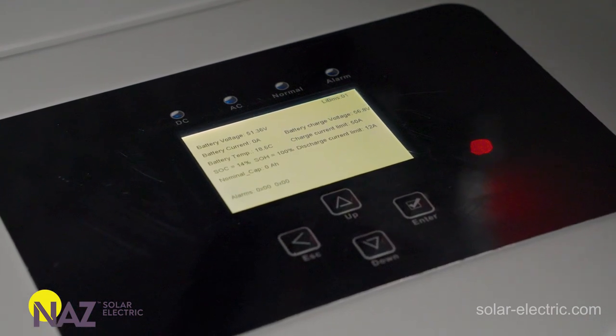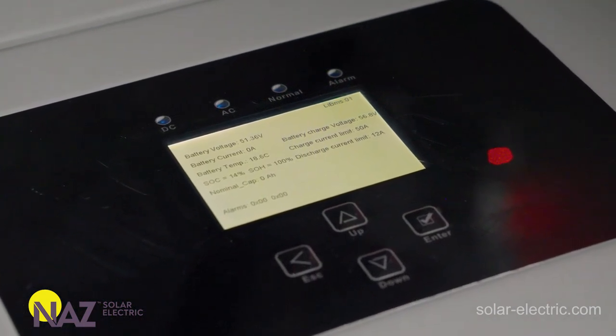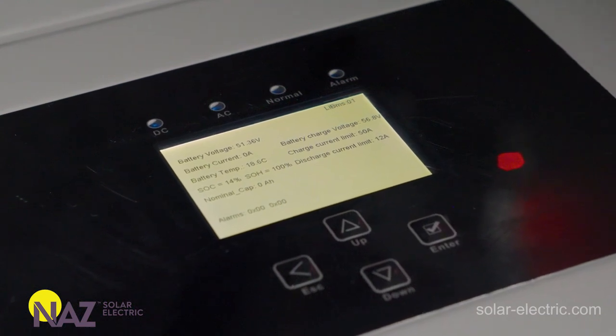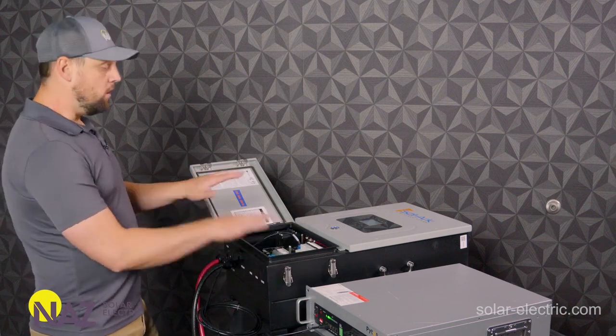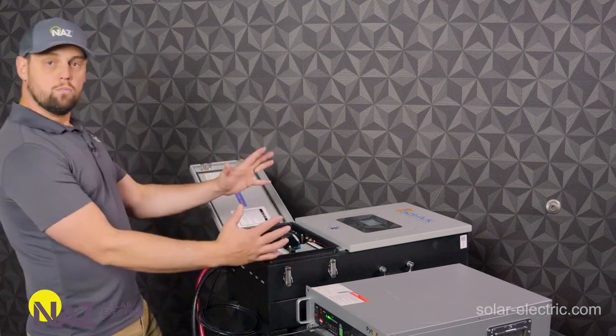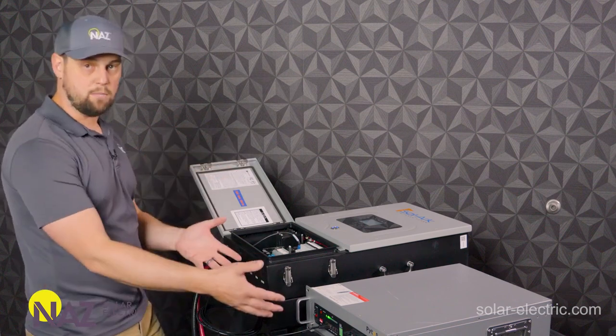We can look right now — the battery is providing battery voltage to the inverter, internal battery voltage. It's providing SOC to the inverter, it's providing internal temperature to the inverter, and it's also defining the charging limits, current limits, and the discharging current limits — all programmed by the battery into the inverter. All the charging settings, everything's done now. I could go install this, facilitate the communications, and everything's done. It's that simple with respect to the batteries.